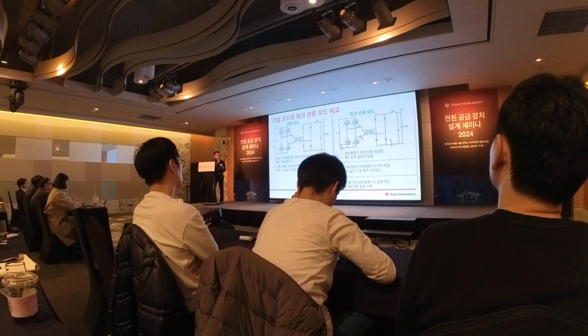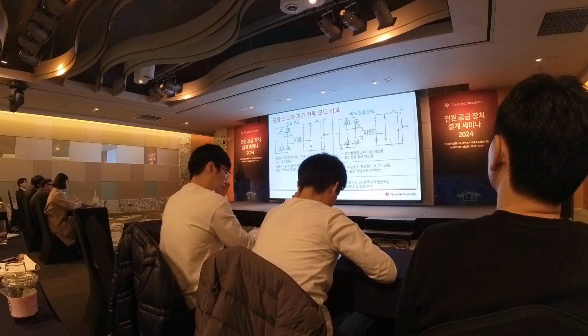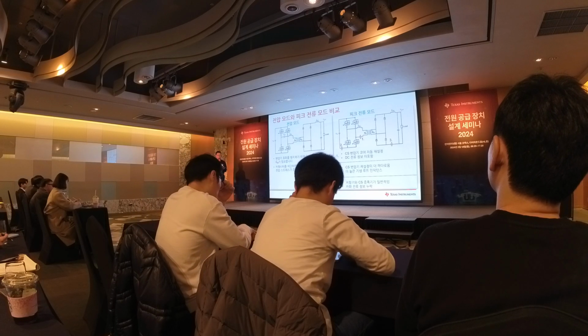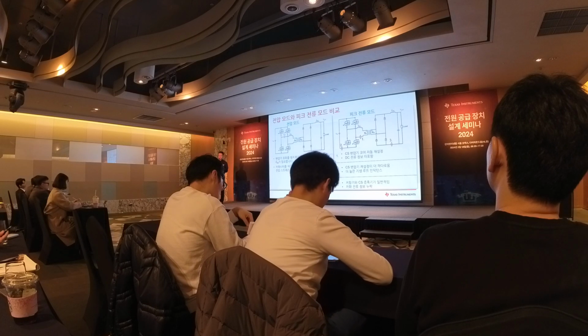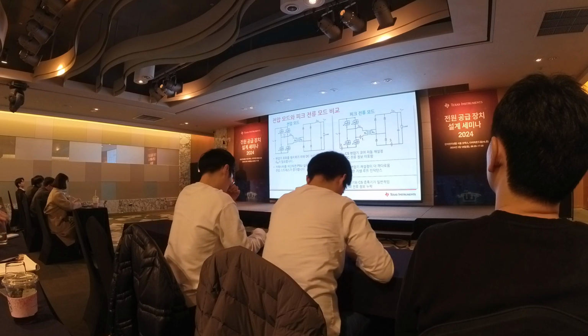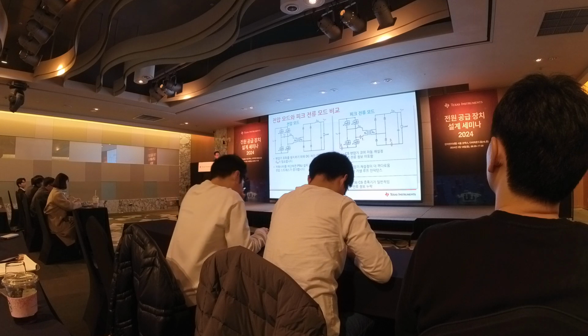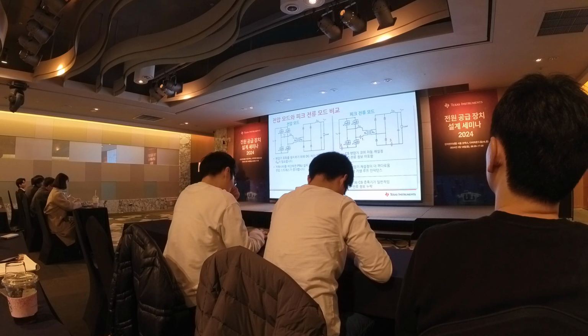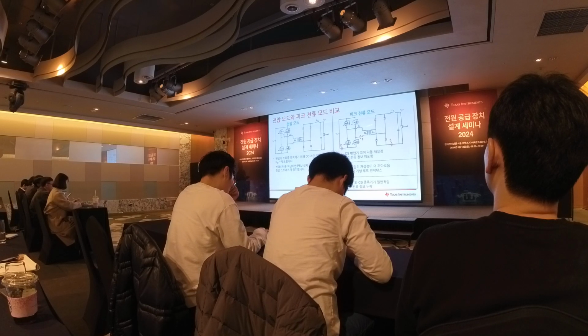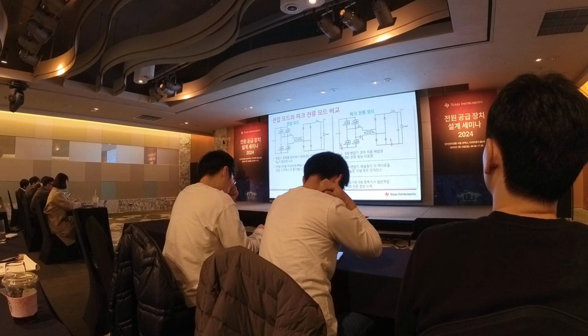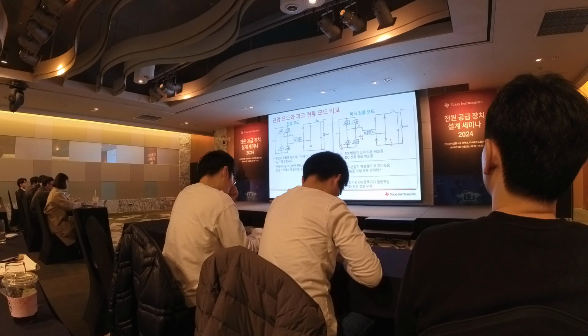If we put the current transformer in location number 1, the current transformer can reset itself easily. But the problem is the current here contains no DC current information. So if the transformer is actually imbalanced with a DC component, sensing at location 1 will not tell us that information.